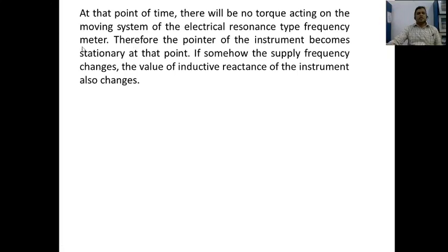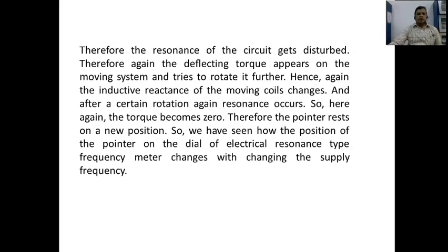If the supply frequency changes, the value of the inductive reactance of the instrument also changes. The resonance of the circuit gets disturbed and a deflecting torque appears on the moving system, trying to rotate it. The inductive reactance of the moving coil changes and after a certain rotation resonance occurs again, the torque becomes zero, and the moving coil is attracted towards the fixed coil. The pointer then rests at a new position, showing how the pointer position changes with changing supply frequency.